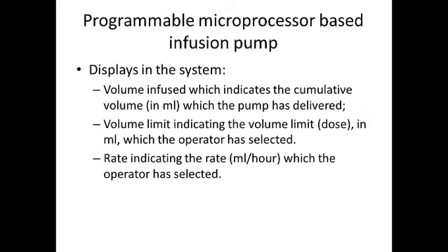Now what is the display in this infusion pump used for? Okay, so the first thing the display shows you is the volume that is infused. Okay, how much volume of the drug is infused inside the body of the patient, which indicates the cumulative volume which the pump has delivered. So it will give you the exact amount, say, 10 ml, 5 ml, how much drug is given to the patient, that is displayed there.